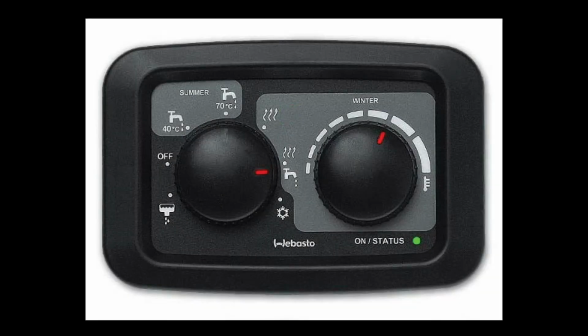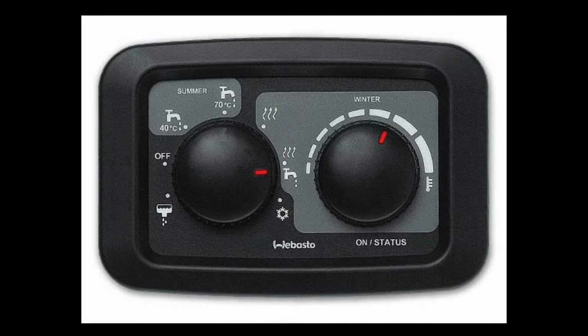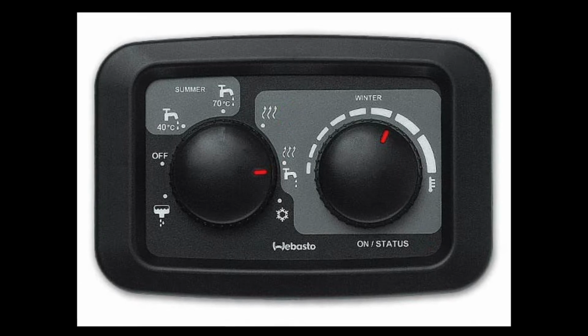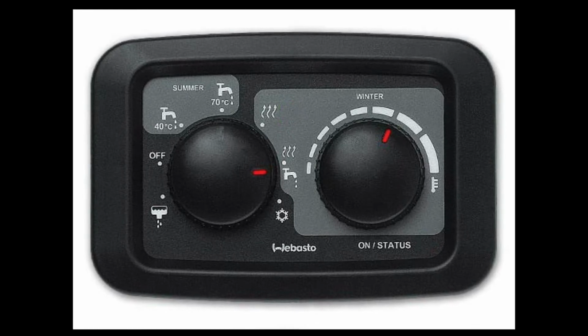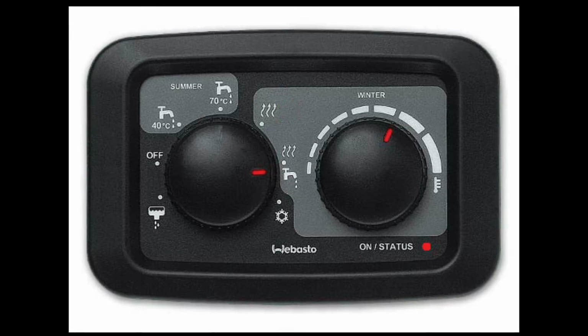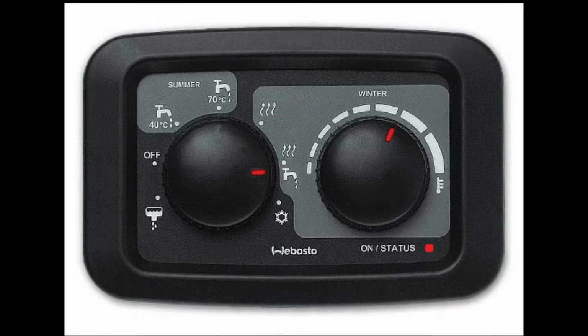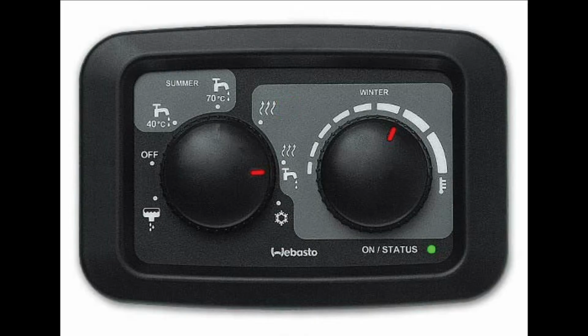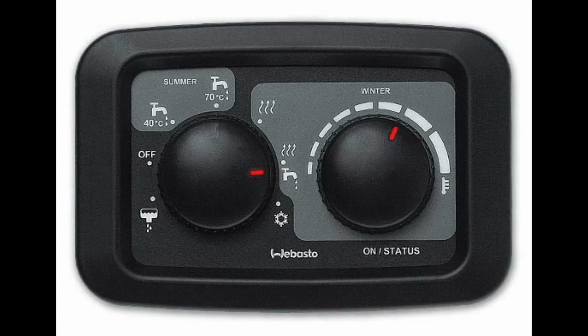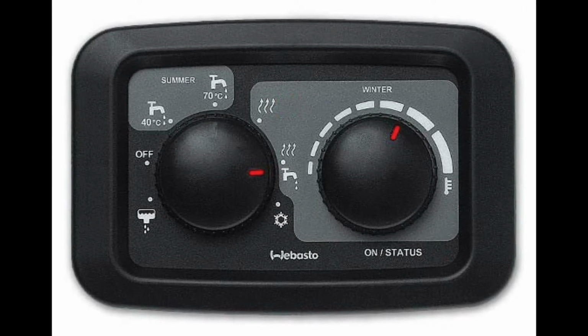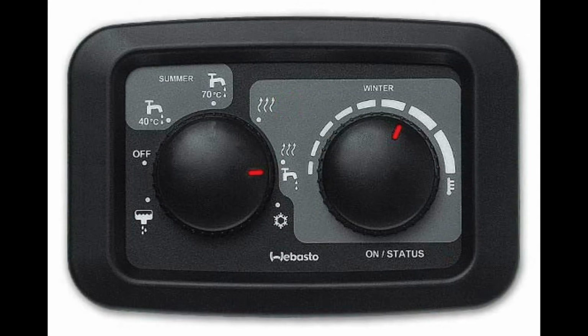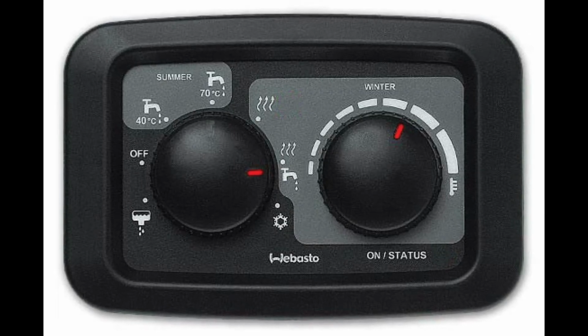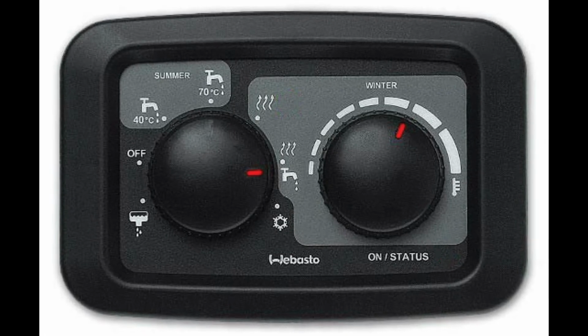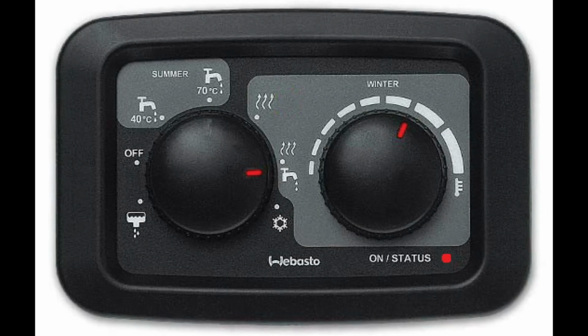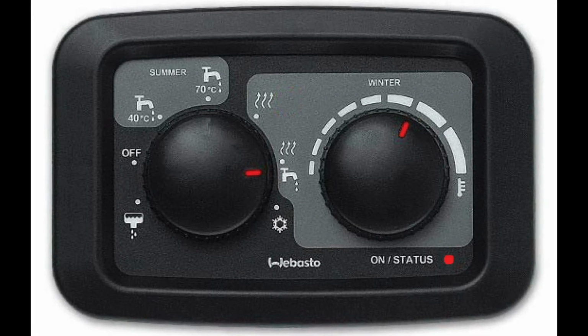A flash code of F04 indicates an issue in the fuel pump or its electrical circuit. It's important to note that if you have the digital control panel, you will see message 6 or message 7 on the screen. We'll be referring to flash code 4 in this video, but the information we're covering would apply to message 6 or 7 as well. If an inspection of the fuel pump and the external wiring doesn't reveal a fault, the next place you'll need to look is inside the dual top's case.